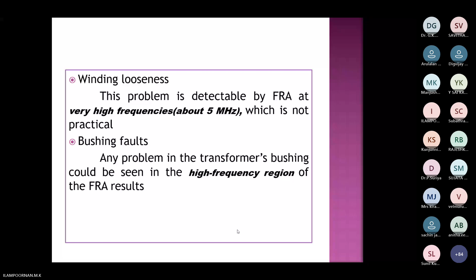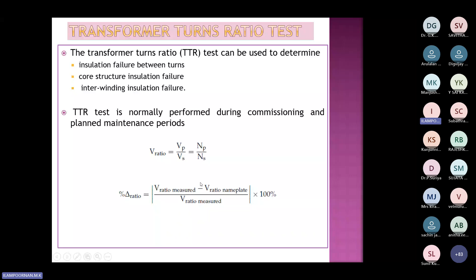That is, in the sense of the offline method, the turns ratio test. It's a simple test. It's like testing the turns ratios. I'm running short of time. So you have to see the change in the ratios. You will have a measured ratio, and the nameplate is the standard ratio, which would have been there when the transformer was manufactured. So the change in the ratio gives you an idea of what the problem is, whether it is an insulation failure, core structure failure, or interwinding insulation failure.